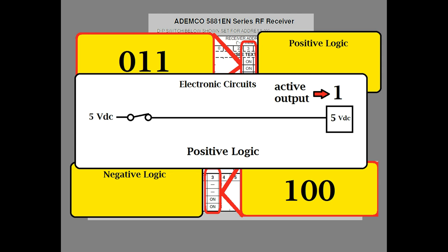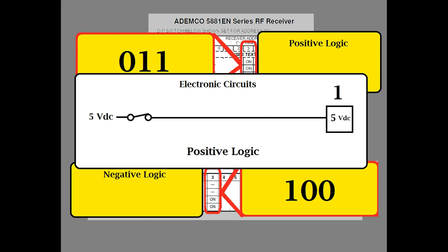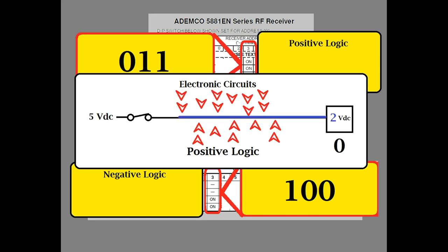There are times, however, this circuit design can have a problem. When it's located near other electronic or electrical things, electromagnetic noise can be introduced into your circuit. This happens most often in automated systems where there's long wire runs. This noise will be interpreted as a voltage, so your circuit could possibly put out a 1 that's false. Or it could go the other direction — a circuit that's putting out a 1 can experience noise that will degrade the circuit voltage to the point where it'll put out a 0 instead of the 1.